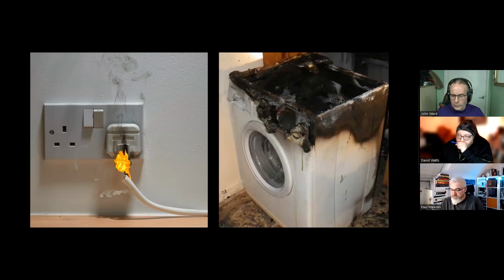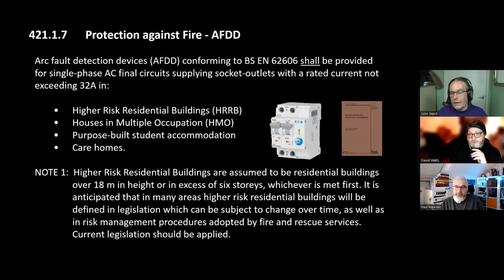One of the more recent developments, and we would be wrong not to say it, is that one of the good risk mitigators of removing the need for AFDD would be to use LSOH cabling. John, you know why? Yeah, LSOH, if you've ever used it, is a horrid cable to use because it's difficult to strip. But the main point of it is when it gets hot or sets on fire, it doesn't give off toxic smoke and it doesn't carbonize in the same way that PVC insulation does. All that happens is that the insulation basically melts, turns to a liquid and disappears. So there's no actual arcing parts there other than the conductors themselves, unlike PVC, which will char and blacken and get worse and worse and then become conductive. So that kind of cabling is very likely to be a thing, certainly in these high-risk environments.